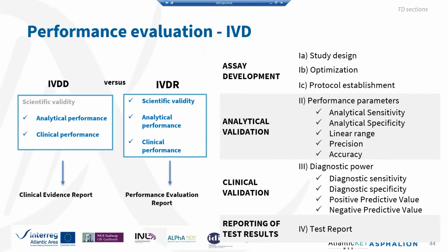This is something particular to IVDs, because obviously in the case of medical devices, you don't have to go through this analytical validation. But as in vitro examination devices, they have to demonstrate that the devices are sensitive, or that they are specific. They only react to certain biomarker, or that they have a linear range. Every one of these steps has to be studied and analyzed.